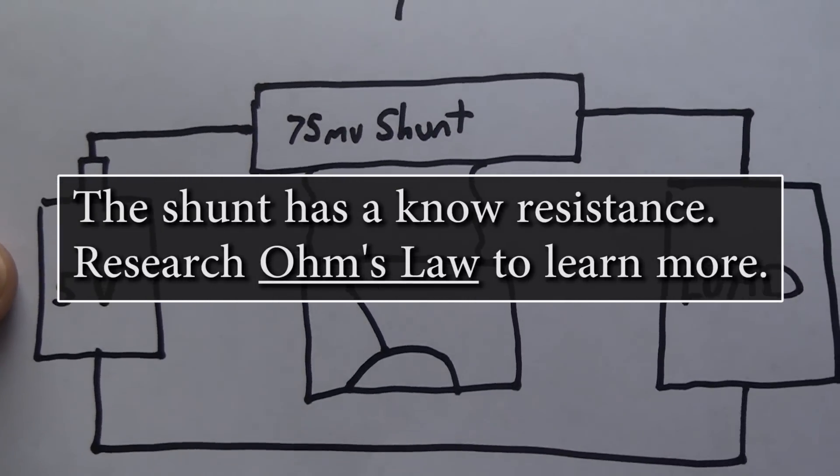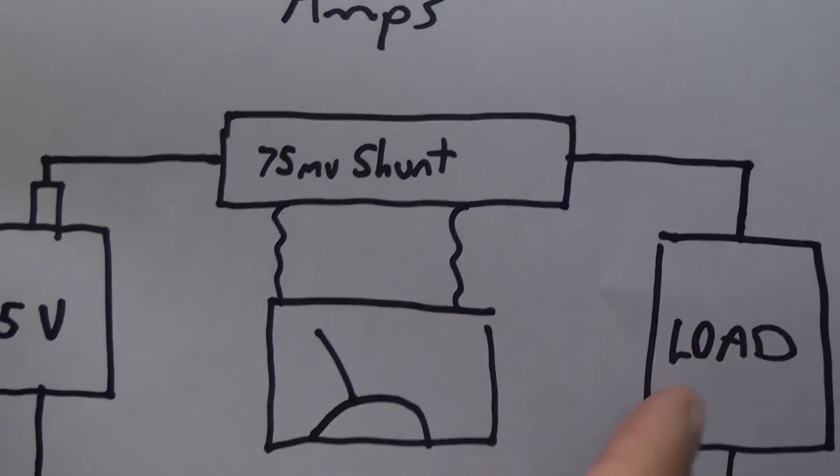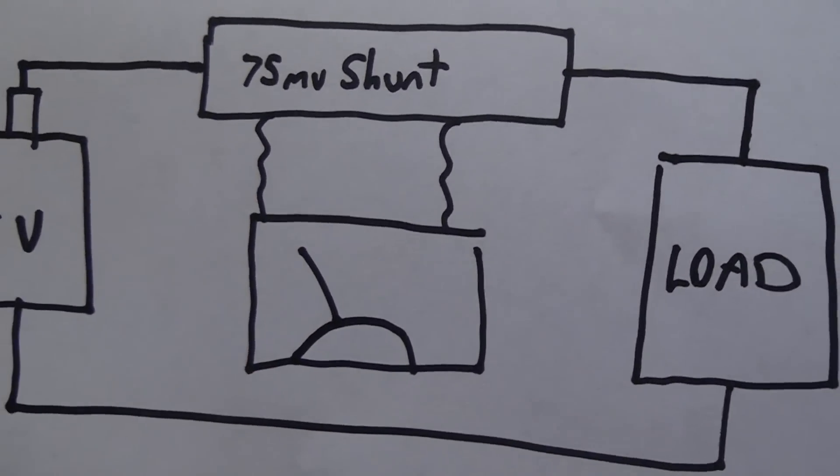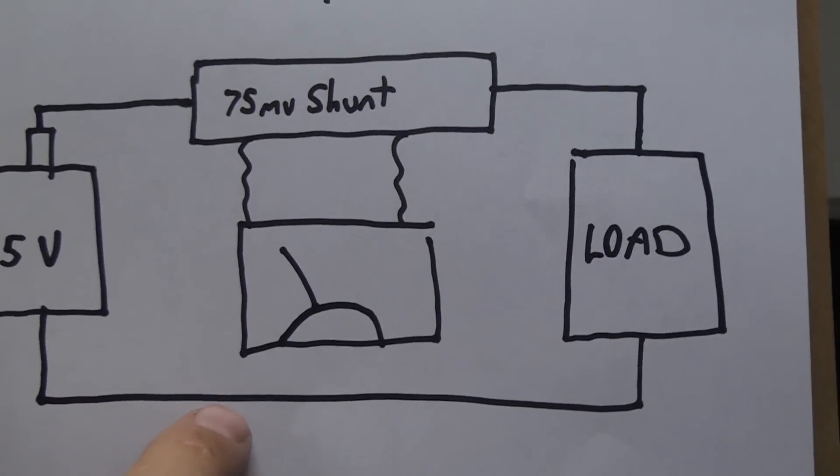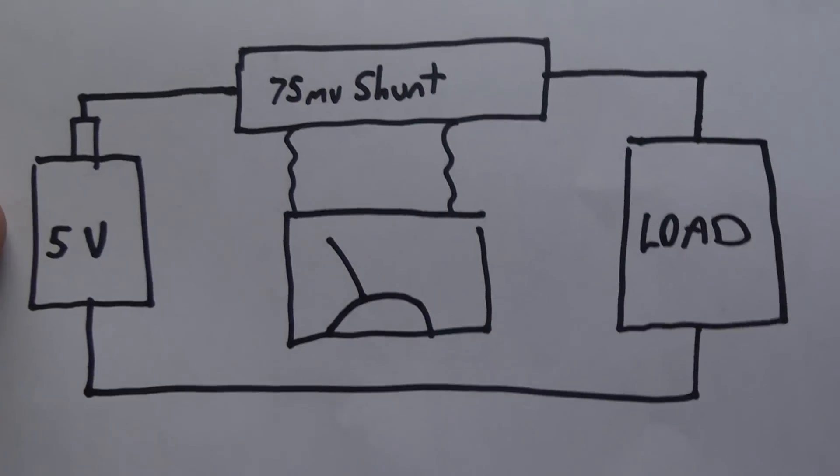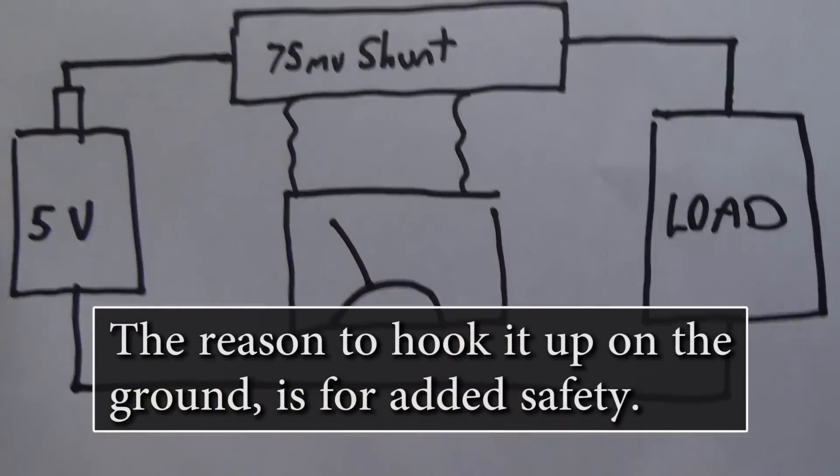If you hook it up and your meter pegs all the way up, you've got your leads switched, so you may need to switch those. Also, I drew the shunt up here on the positive, but I believe best practice is to have your shunt in line on the negative. So your two little squiggly wires would come down here - this is where your shunt would be.